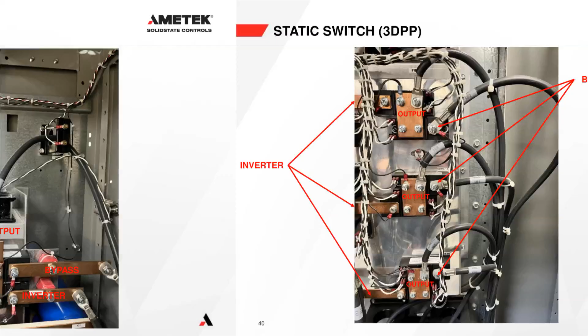And for a three-phase system, it's a little bit more complicated, but you can see once again we have our inverter A phase, B phase, and C phase going in, and then we have a static switch. So basically we have an A phase static switch, a B phase static switch, and a C phase static switch. And they all get the same gate drive signal sent to them at the same time.